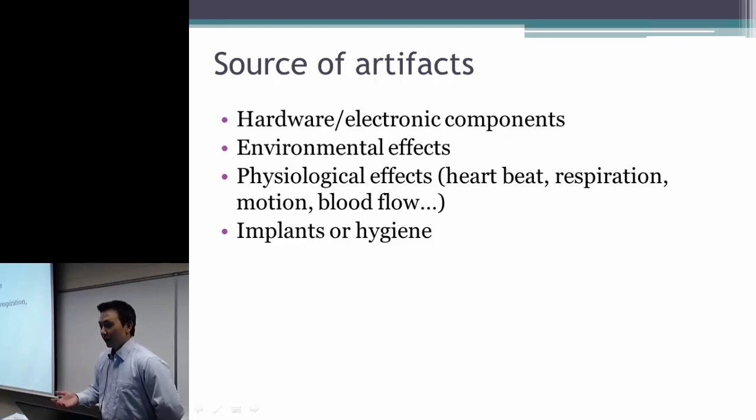Once we scanned a person on his head, and we found that the image was so blurry. We had no idea how to explain it. Then another person went in and was scanned, and everything turned out fine. Later, one of the clinicians suggested that the subject go wash his head. So after using shampoo and washing, and squeezing the water from the hair, we put him back in the scanner and did the scan again.